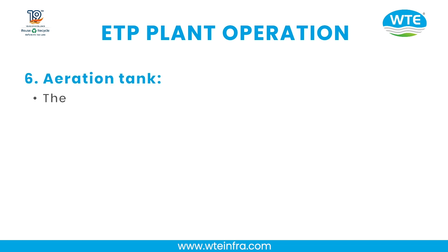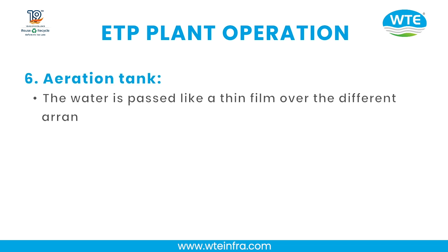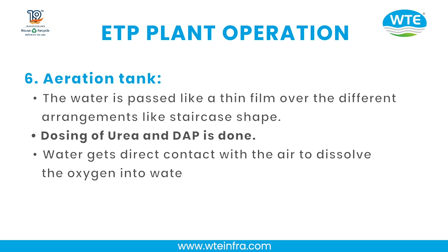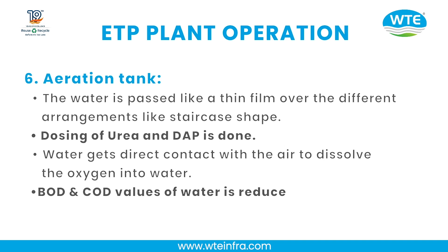Step 6 — Aeration Tank: Water is passed like a thin film over different arrangements in a staircase shape. Dosing of urea and DAP is done. Water gets direct contact with air to dissolve oxygen into the water. BOD and COD values of the water are reduced by up to 90%.